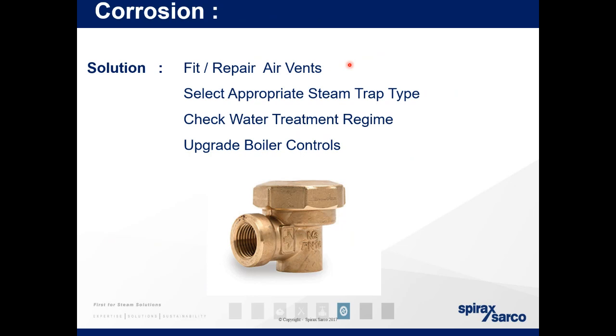As it says here, select the appropriate steam trap type. We have many different steam traps, all for different applications. For instance, if you were doing heat tracing in the oil and gas industry, you probably wouldn't be returning that condensate. So you would use something like a bimetallic trap, because that will introduce what we call a cooling leg before the trap. There is a volume of water, maybe 1 or 2 meters, sat behind the trap before it's discharged. That allows you to remove as much of the heat as possible before you get rid of that condensate.